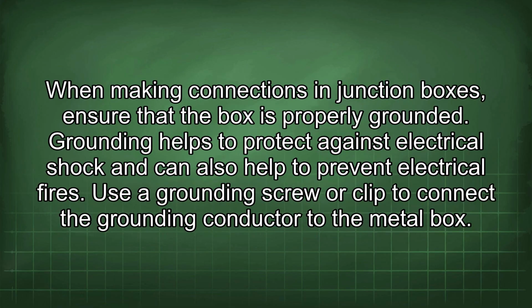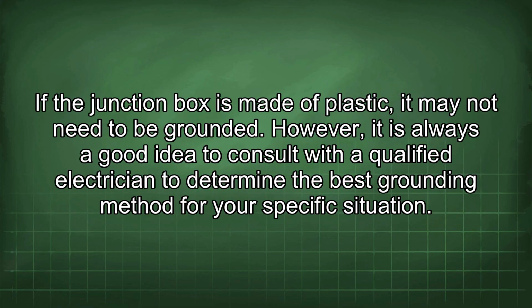When making connections in junction boxes, ensure that the box is properly grounded. Grounding helps to protect against electrical shock and can also help to prevent electrical fires. Use a grounding screw or clip to connect the grounding conductor to the metal box. If the junction box is made of plastic, it may not need to be grounded.